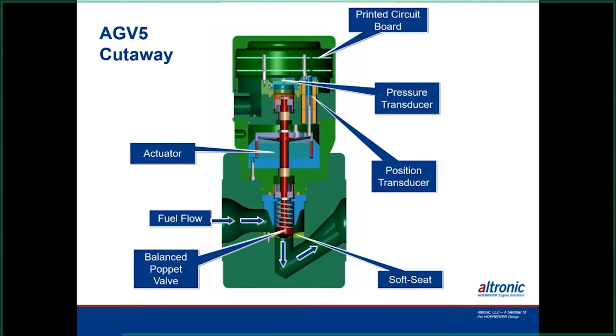This gives you a little cutaway on it. The board I'm talking about, you see these boards in here, and this is a pin that will move up and down around these boards. If these boards get moved at all because you loosen up the screws, it knocks off the calibration of this positioner, so keep that in mind. We also made a modification down here where it flows more gas on the dash 2 valves. Again, if that's something you think you could look into, see whether your valves have the latest modification that can do that. It's a very simple valve that works extremely well.